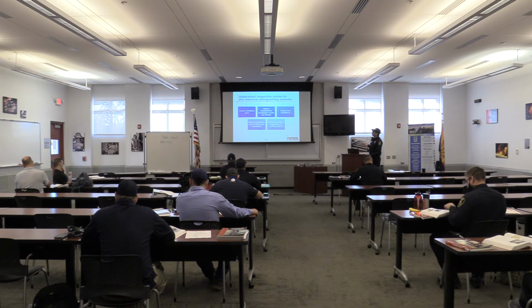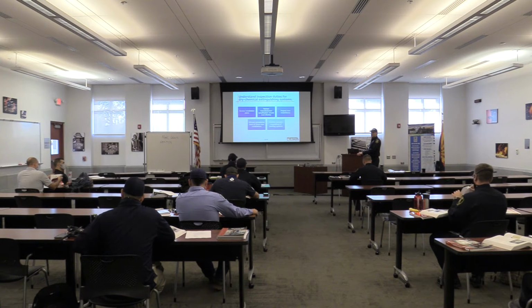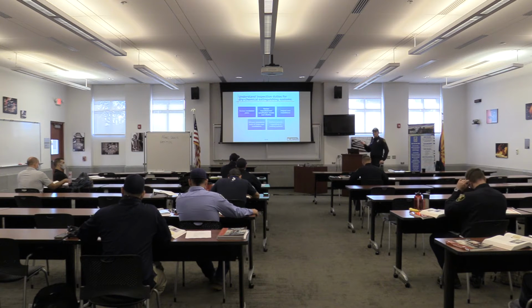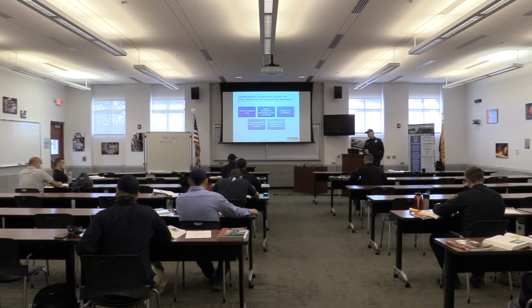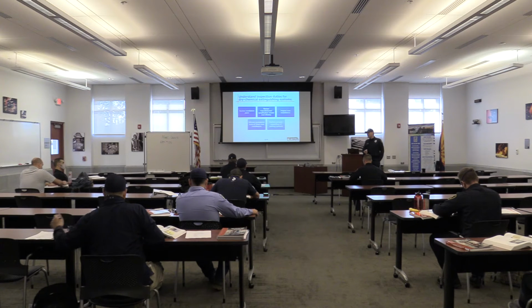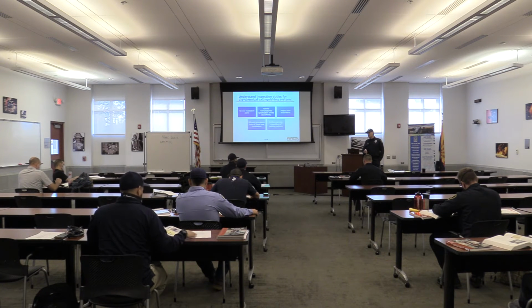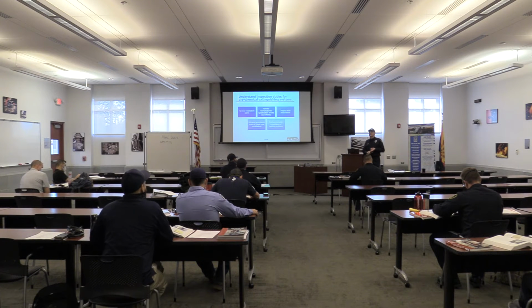All right, so as far as the inspection duties for dry extinguishing systems, the book does put a lot of onus on the fire inspector to inspect the systems. Part of your inspection is to look at the system, but what we require when we run into these systems is for the owner or occupant to provide us with an annual inspection report, the most recent one. And at the very least, it should have been within the last year. Sometimes, depending on the system, it may be a 6-month requirement for inspection testing.